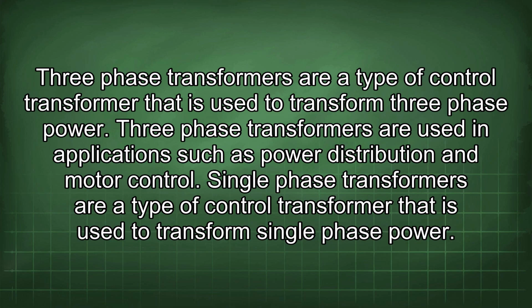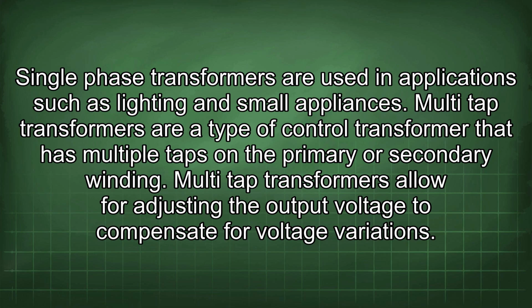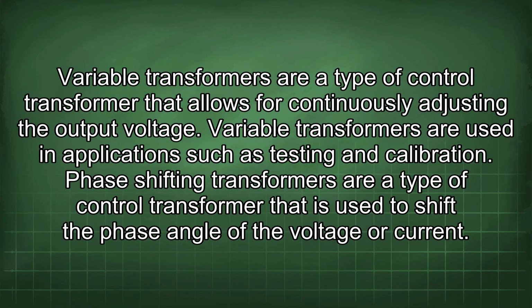Single-phase transformers are a type of control transformer that is used to transform single-phase power. Single-phase transformers are used in applications such as lighting and small appliances. Multi-tap transformers are a type of control transformer that has multiple taps on the primary or secondary winding. Multi-tap transformers allow for adjusting the output voltage to compensate for voltage variations. Variable transformers are a type of control transformer that allows for continuously adjusting the output voltage. Variable transformers are used in applications such as testing and calibration. Phase-shifting transformers are a type of control transformer that is used to shift the phase angle of the voltage or current.